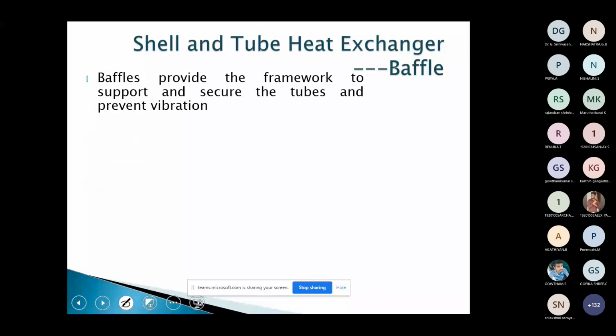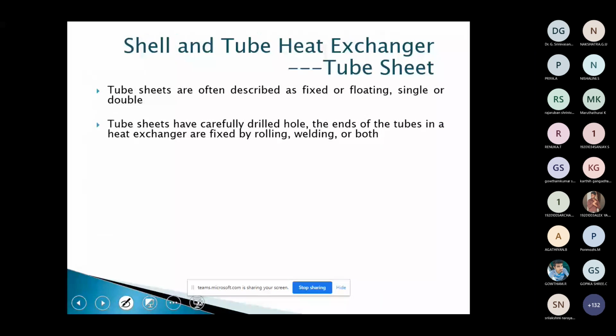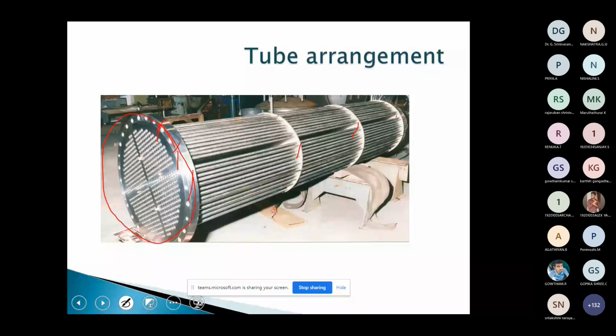So I have to show the tube sheets. This is the tube sheet in which the tubes are mounted. Here you can see that it is welded. If it is welded, then it is called a fixed head.